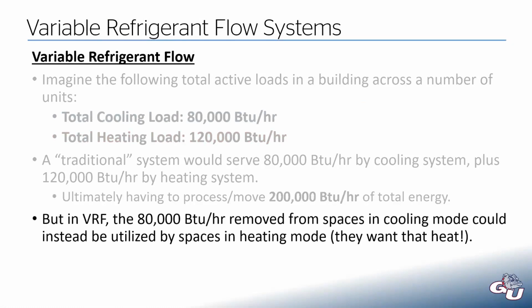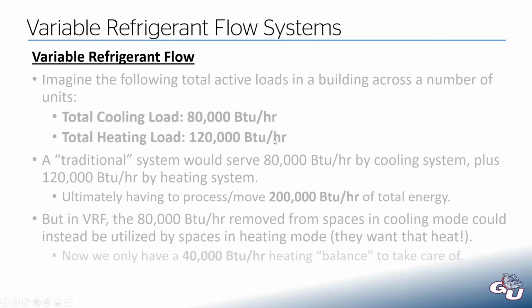So we have VRF, and now this 80,000 that we are pulling out of spaces to provide cooling, we can now use in these spaces that want that heat energy. And what that leaves us with is this 40,000 BTUs per hour of a heating balance that we now have to take care of. So we went from 200,000 to 40,000.